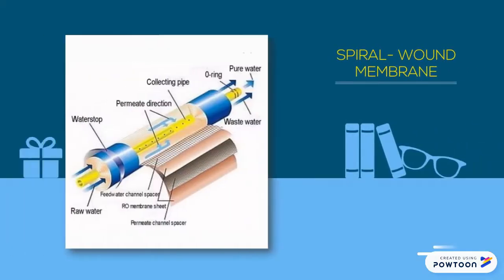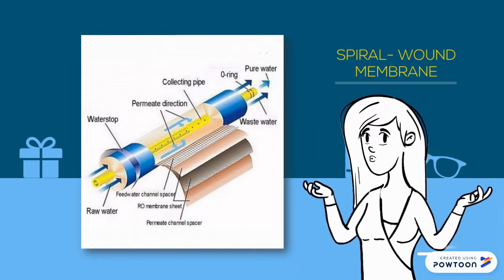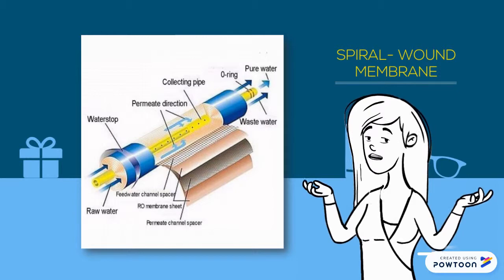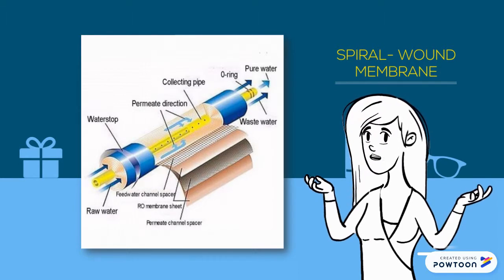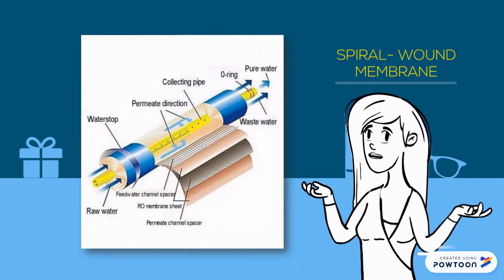Spiral wound membrane consists of membranes, feed spacers, permeate spacers, and a permeate tube. First, a membrane is laid out and folded in half with the membrane facing inward. A feed spacer is then put in between the folded membranes forming a membrane sandwich, providing space for water to flow between the membrane surfaces. Next, the permeate spacer is attached to the permeate tube, and the membrane sandwich is attached to the permeate spacer using glue. The process is repeated until all required permeate spacers have been attached, and the finished membrane layers are wrapped around the tube, creating the spiral shape.